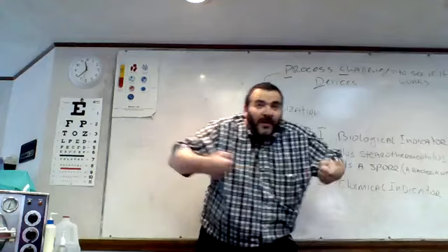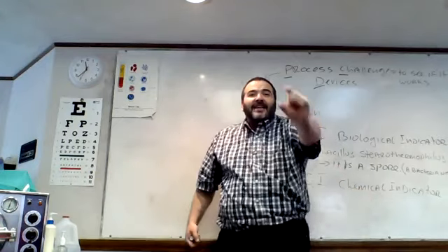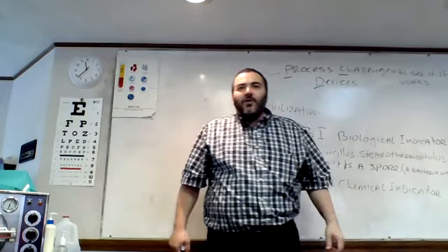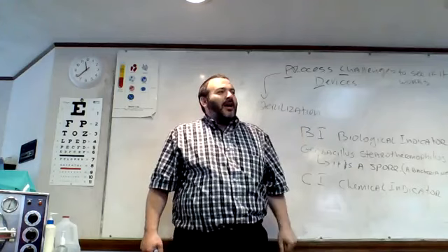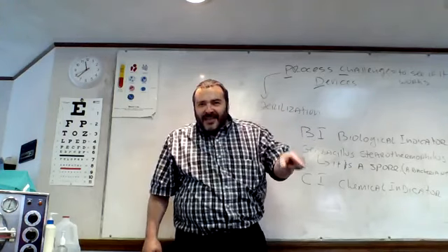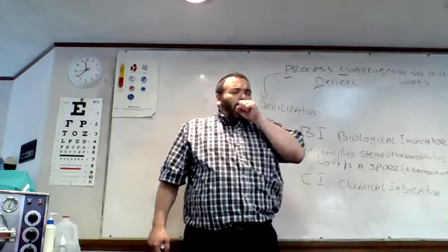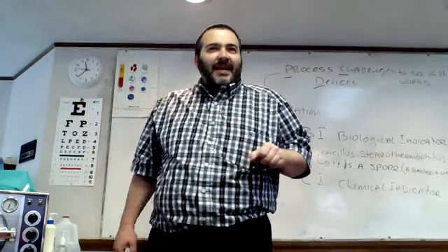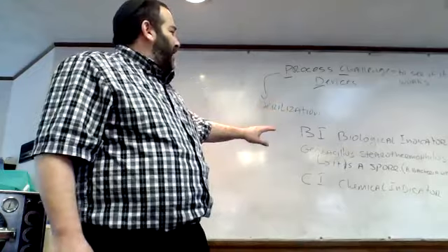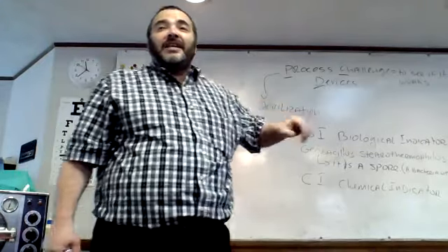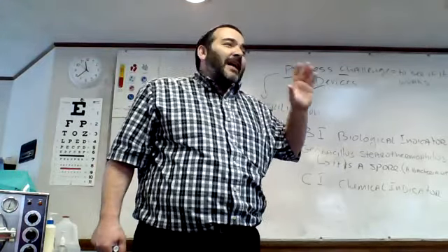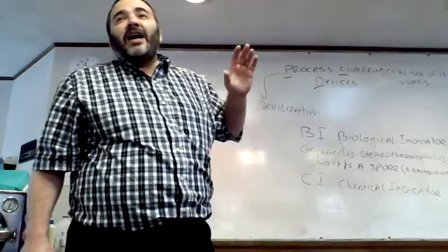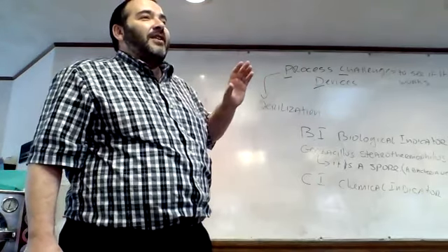And when they open it up, inside there they see that other little thingy that I gave you, and they say, yeah, if that turned a color, the inside of the package was also duly exposed to the sterilant. Does that make sense? So the chemical indicator, together with a biological indicator, give us some degree of satisfaction that we're providing sterile instruments.